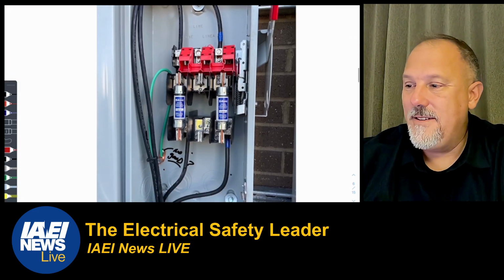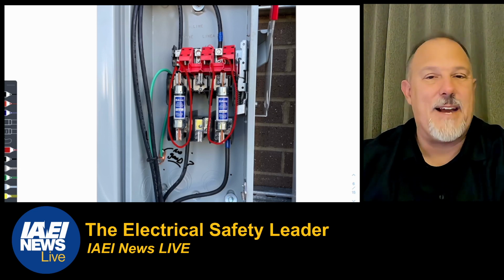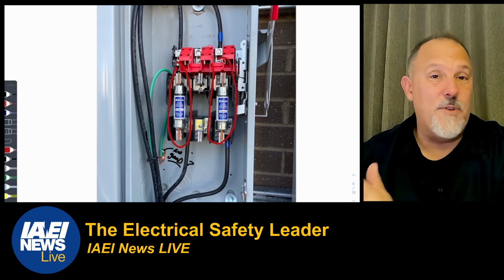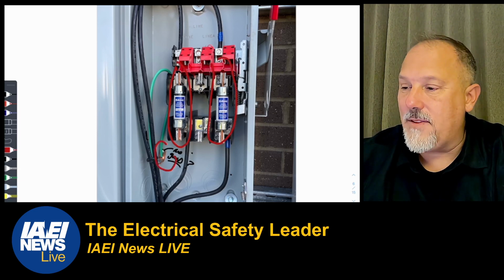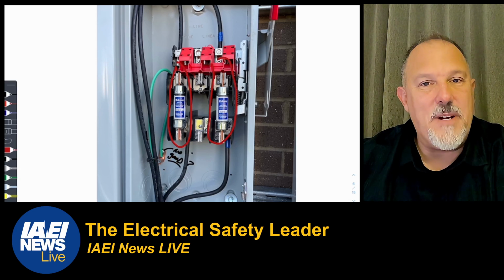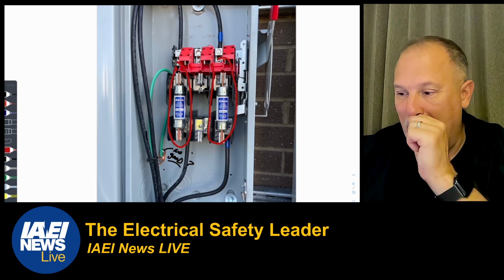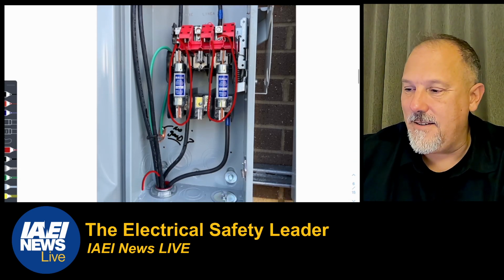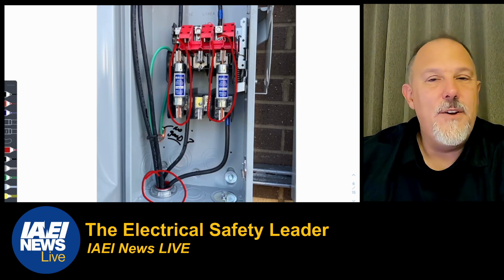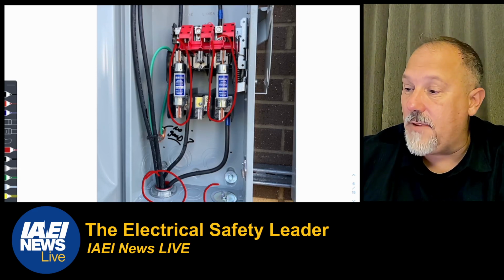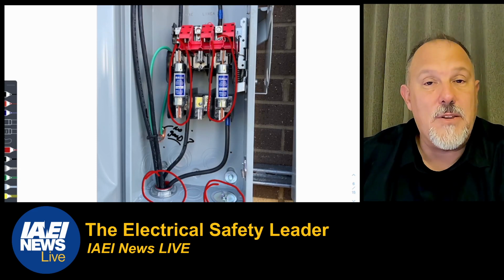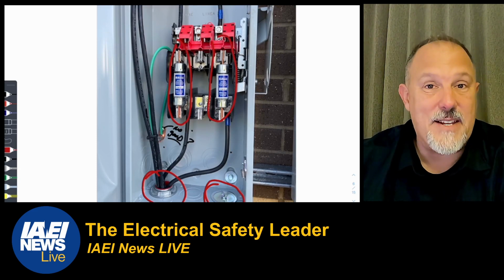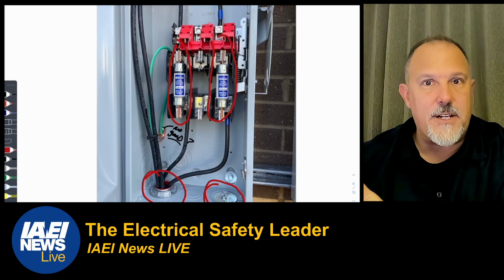In the switch, right? So they're using the outer two legs of the switch. Why are they using the outer two legs? Is that what the manufacturer tells you? What's the reason for that? How about the grounding and that screw? How many threads am I supposed to have? How about this fitting down here? Where in the code does it tell you what those fittings need to be? How about where in the code does it tell you to plug those holes? How about NFPA 70E? And we didn't even get into the arc flash analysis of all this.